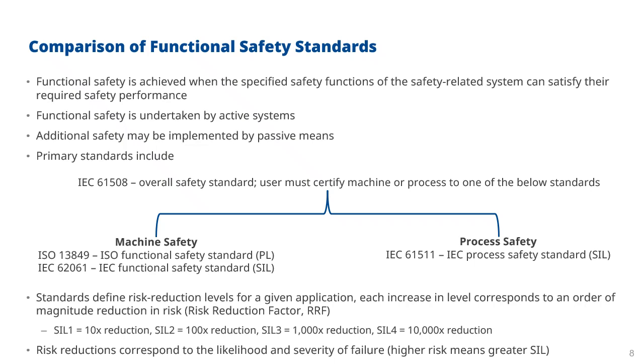So for machine safety, we've got ISO 13849, which gives us an ISO functional safety standard related to performance levels. So you might hear of things like PLD, so that's performance level D, which is a particular level of safety. There's also the related IEC 62061, which is an IEC functional safety standard, and that uses safety integrity levels. So you might see SIL 2 or SIL 3. For process safety, the standard we use is IEC 61511, and that's a process safety standard which uses safety integrity levels. But it's important to note that although we've got two different standards here, both implementing safety integrity levels, the way we calculate those safety integrity levels and the actual standards and how they apply might be different in each case. So just because you've got something that's safe under machine safety standards doesn't mean it's safe under process safety standards or vice versa. They are different standards and they need to be applied differently.